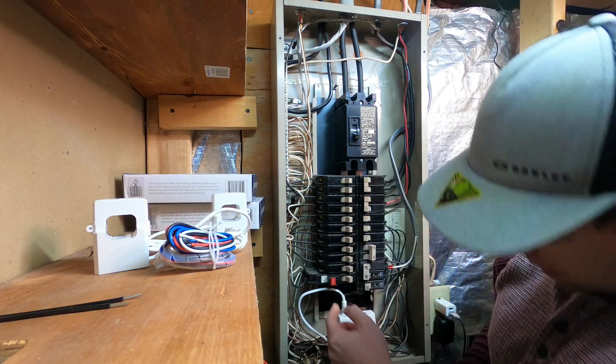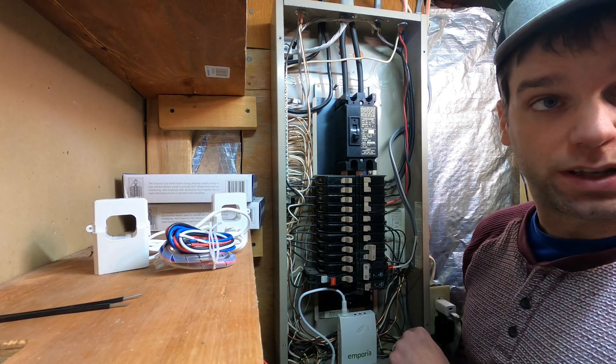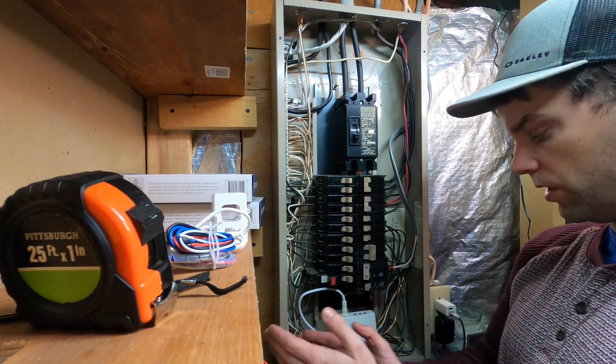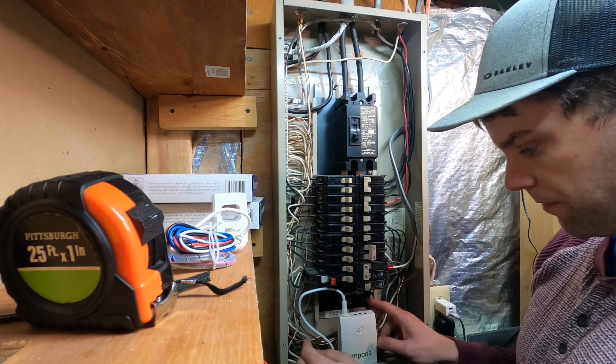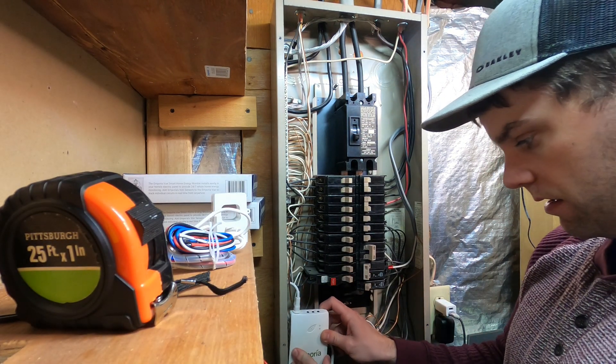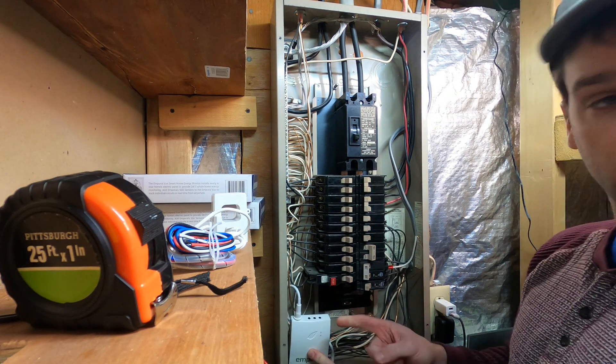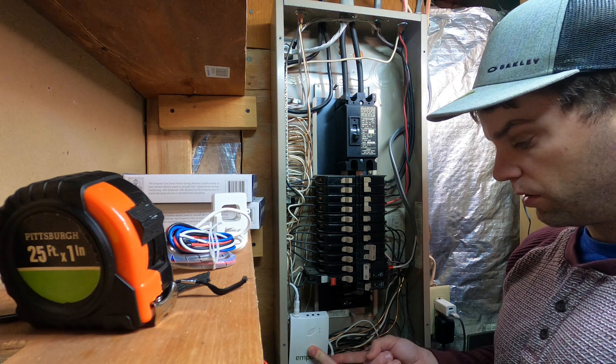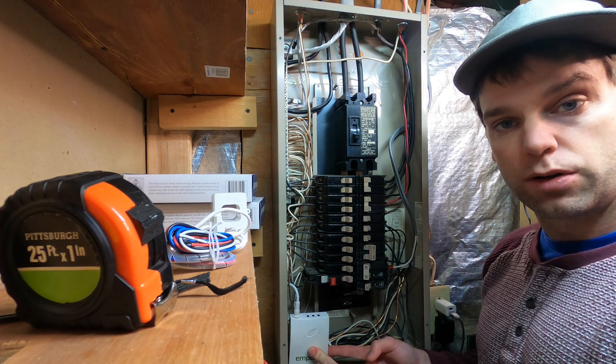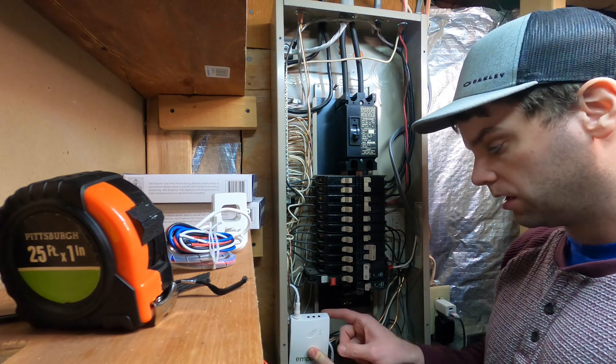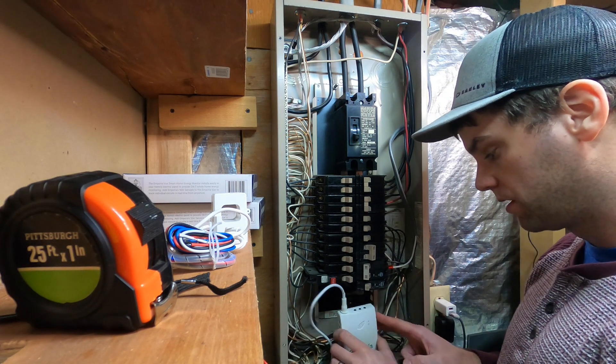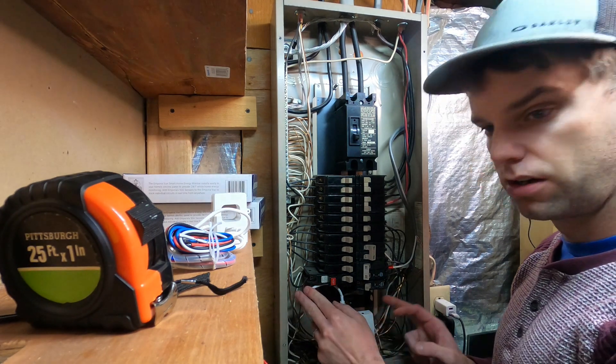It looks to me like the minimum installed height is about six inches with bending this wire without getting it too sharp of a bend. So you're going to want to make sure you have six inches from the bottom of your panel up until the top there. Got a bit more clearance on this side, but you can see if I was using the breakers all the way to the bottom, I wouldn't be able to use this unit. Maybe locating it off to one side or the other might help. You can see I can tuck it over here. I'm not sure though. We'll see in a minute how all these connections work if I'd be able to fit everything in. For now, I don't need that space so I am going to leave it here right in the center.